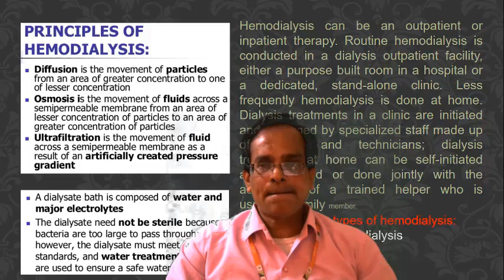What is conventional hemodialysis? Conventional hemodialysis is usually done 3 times per week for about 3 to 4 hours for each treatment, sometimes 5 hours for larger patients, during which the patient's blood is drawn out through a tube at a rate of 200 to 400 milliliters per minute. The tube is connected to a 15, 16 or 17 gauge needle inserted in the dialysis fistula or graft, or connected to one port of a dialysis catheter. The blood is then pumped through the dialyzer and the processed blood is pumped back into the patient's bloodstream through another tube connected to a second needle or port.